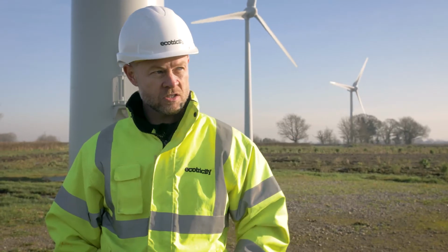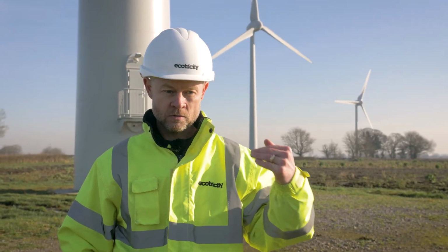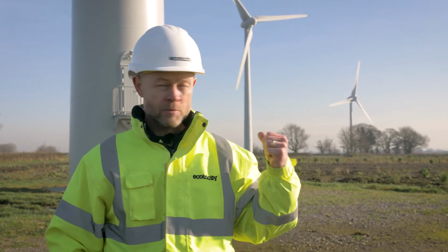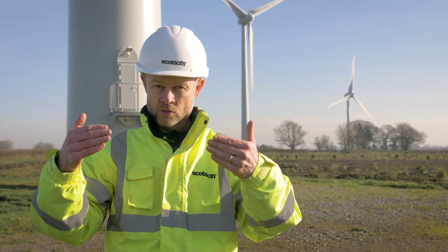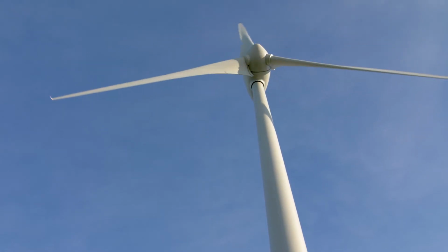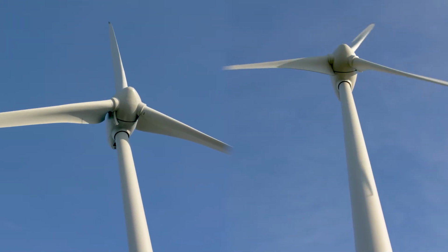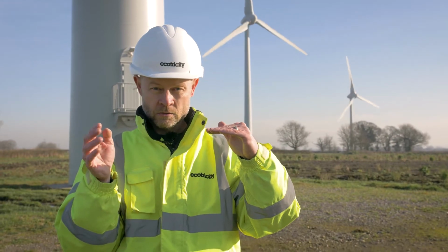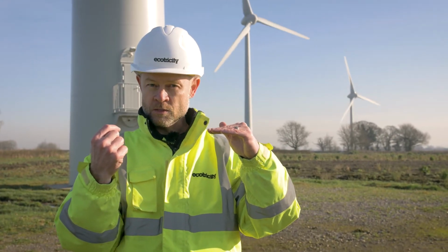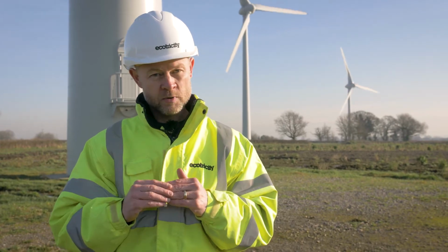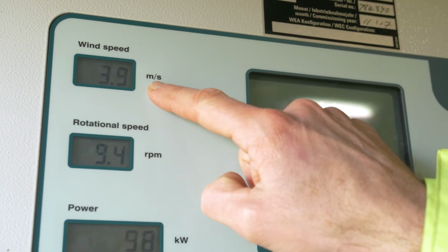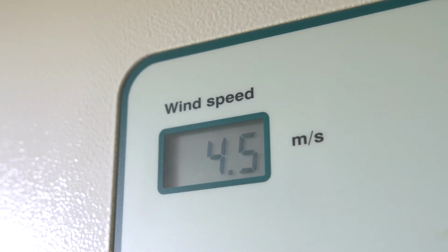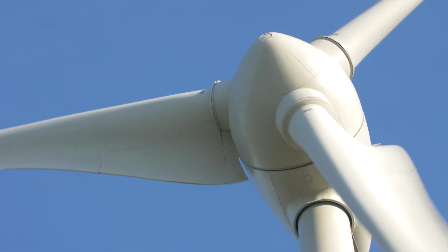So these are 65, 69 meters up in the air, so the wind speed and the wind resource is different up there. And you see behind me the blades are facing quite flat to the wind. When there is no wind, the blades are quite a thin profile. And then the anemometer at the top of the wind turbine, which measures the wind speed and the wind direction, will determine how much wind speed there is. Once it gets to about 2.5 meters a second with this particular model, the blades will start feathering themselves in to get a fat face against the wind. That then generates the movements of the blades.